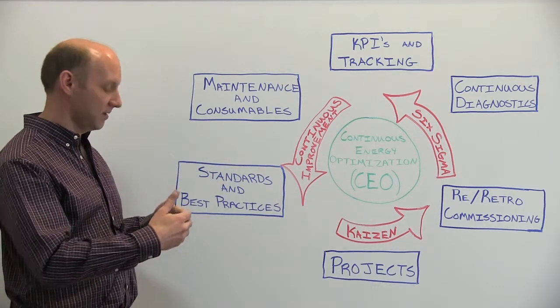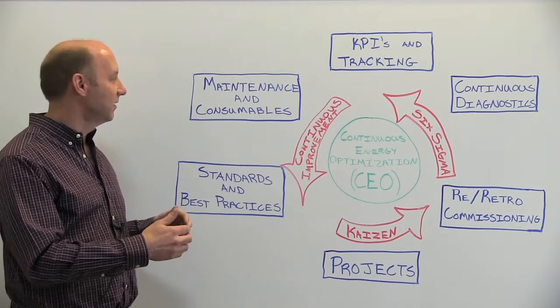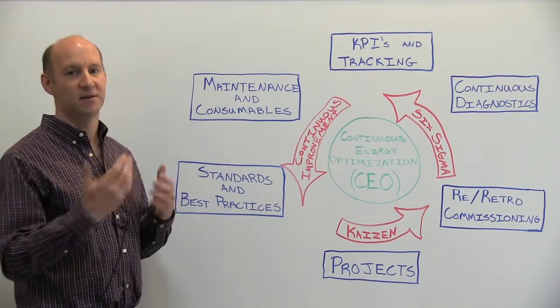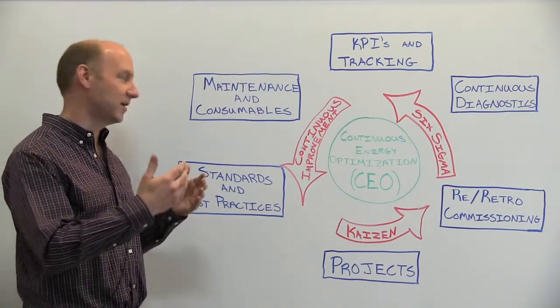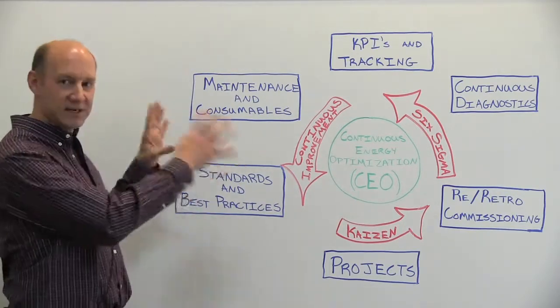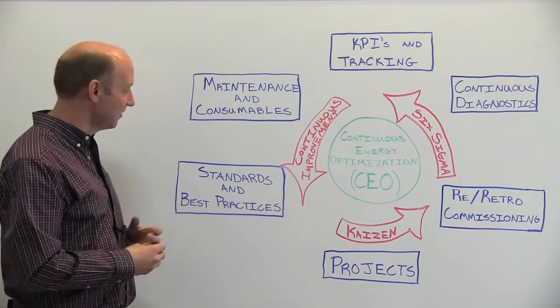If you have a filter that creates a high pressure drop in the airstream, then that can actually cost you energy. In some instances, if it's fed with a variable speed fan, that can actually save you energy. So understanding those, they have a real impact on the facility, not just in first cost, but in energy costs.